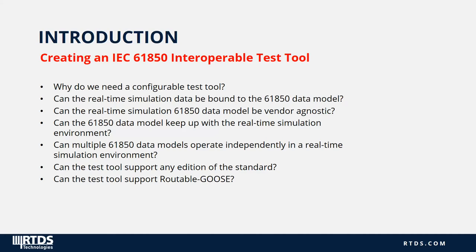Can the real-time simulation data be bound to the 61850 data model? Yes, the components of a power system simulation can be bound to a 61850 data model's logical nodes in such a way that the data model reacts as if in the real world. Can the simulation 61850 data model be vendor agnostic? Yes, the simulation tool can be configured in such a way that it consumes and mimics any valid SCL file.